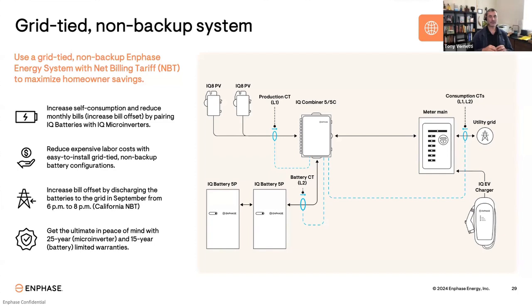So as we mentioned, we've got several different configurations. I'm just going to go over the two most popular battery configurations, which are a grid-tied battery for non-backup. These are especially popular in California right now because of the net billing tariff, the current iteration of net metering, basically, where it's not called net metering anymore because it's technically not that. And there is very little value to exporting solar power back to the grid during the middle of the day when there's excess solar. So a battery is really key here for storing up that energy during the daytime, and then using that energy during the peak period in the evening to avoid paying peak rates to the utility.